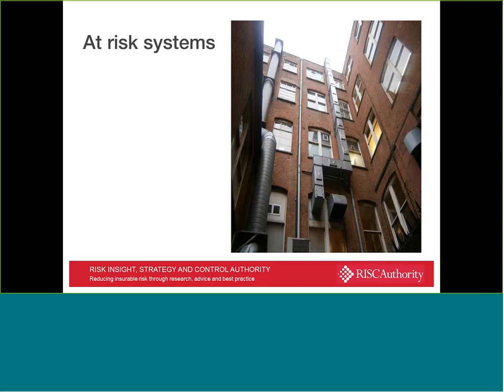In this situation, you can see there's a relatively long section of ductwork external to the premises, and that's something we also try to avoid, simply because when the ductwork gets cold, that increases the rate at which oil and grease will build up because it won't be extracted from the system as effectively. It's not uncommon in those circumstances to actually insulate the ductwork to enable the system to work effectively. And of course, because we've got grease and oils and dust being passed through the duct, there should be no fire dampers in the system itself.